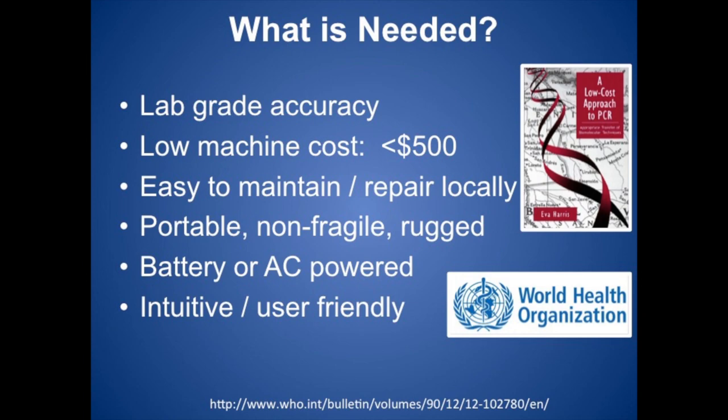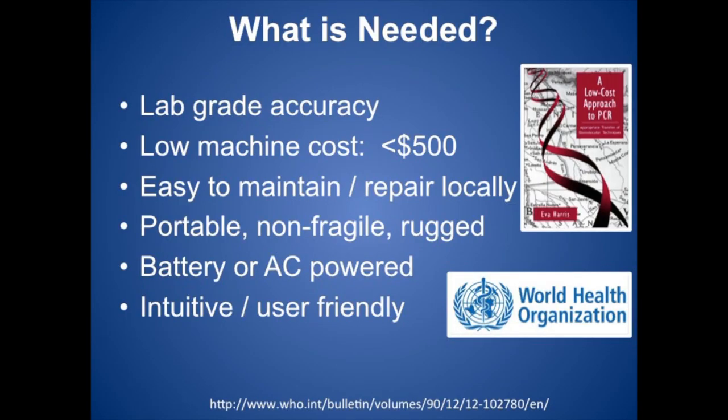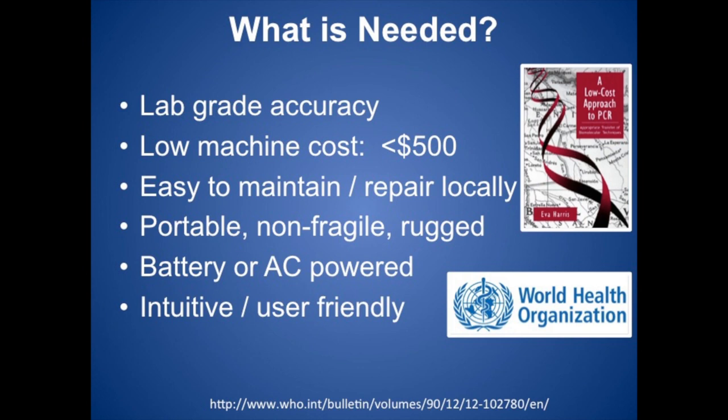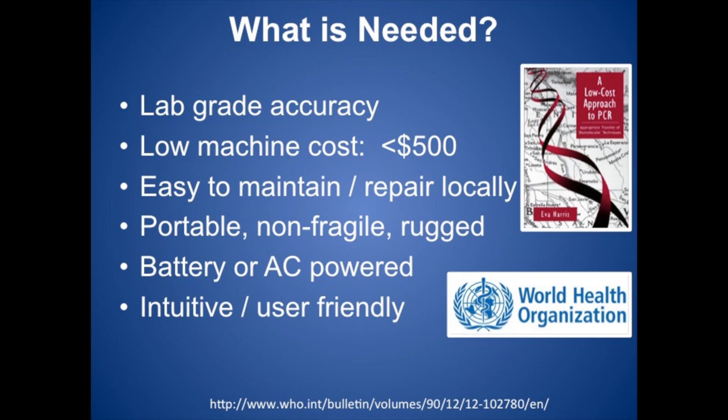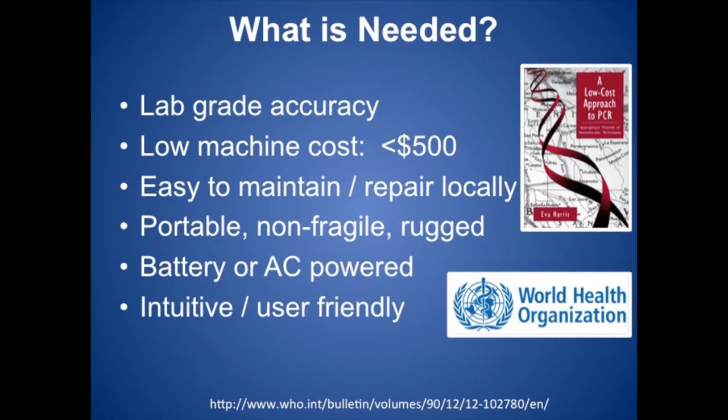So what is needed to make a machine accessible to developing nations? First of all, it needs to have lab grade accuracy — you cannot sacrifice the accuracy of the machine, otherwise PCR will not be effective or worthwhile. Second, it must be affordable and inexpensive so it can be accessible by developing nations that don't have large amounts of funding. Next, it needs to be easy to maintain and repair locally because it can cost exorbitant amounts of money to constantly import and export the machine. It also needs to be portable, non-fragile, and rugged so it can survive any terrain. It must be battery-powered or AC-powered so it can work in on-site implementations and integrate with labs that have access to good electricity. And lastly, it must be intuitive and user-friendly, because many donated thermocyclers go to waste simply because they're not intuitive and users don't know how to perform PCR.